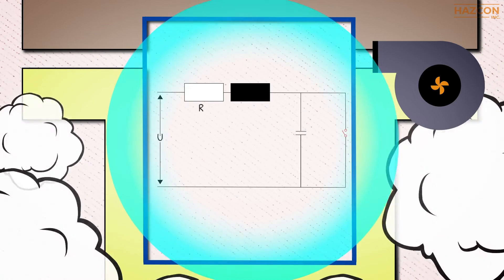In summary, the purging and pressurization technique permits ignition-capable electrical equipment to be installed in a hazardous location when contained in a suitable enclosure. The enclosure first must be purged to flush out the existing gases and then pressurized to prevent the ingress of the exterior explosive atmosphere.